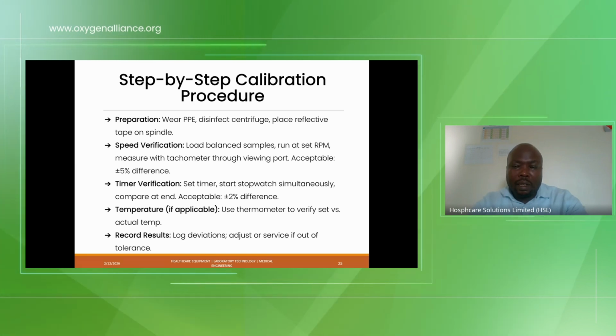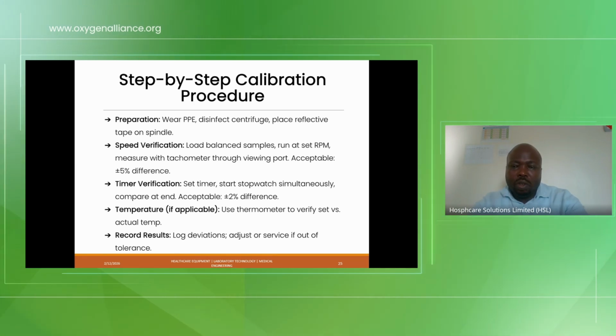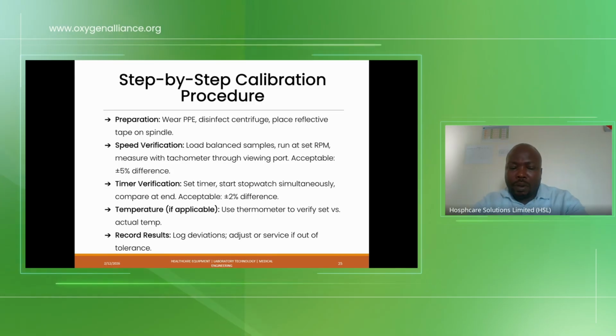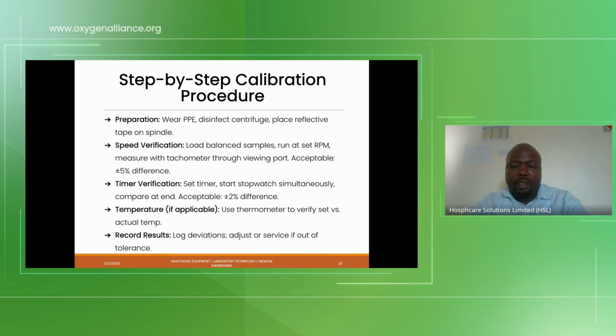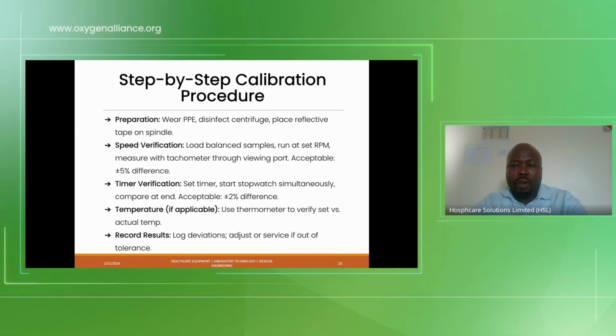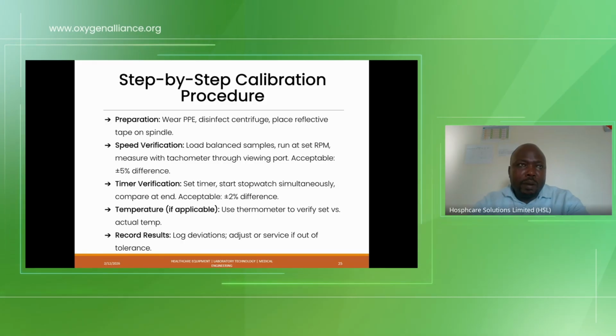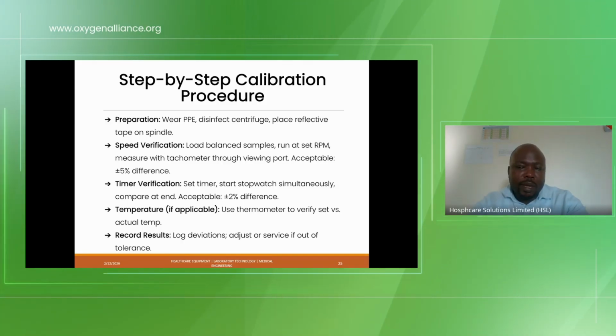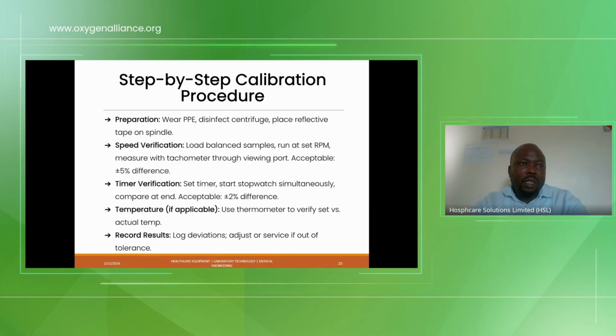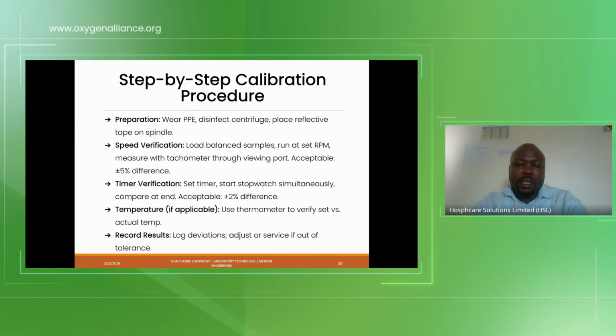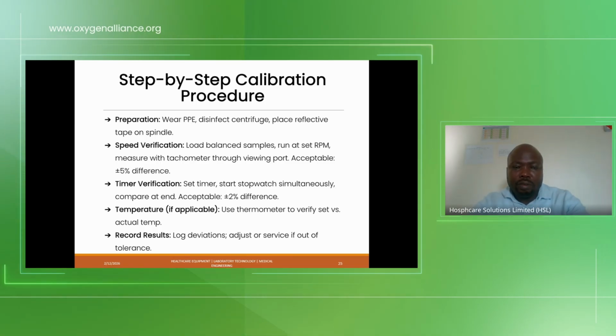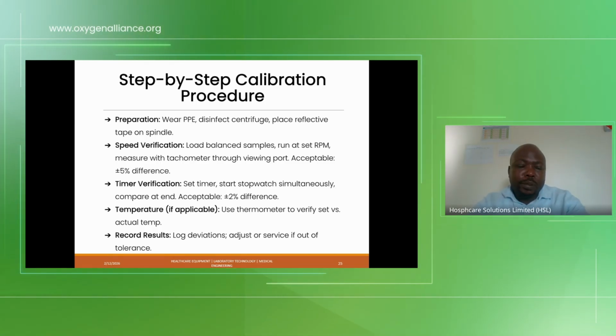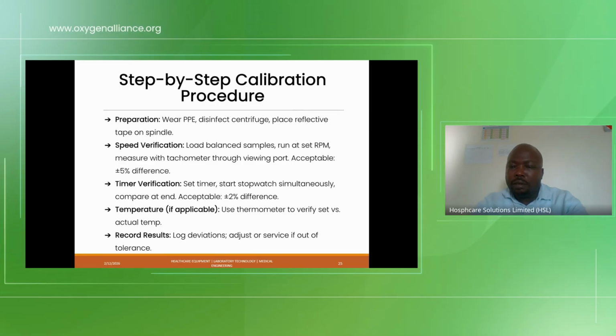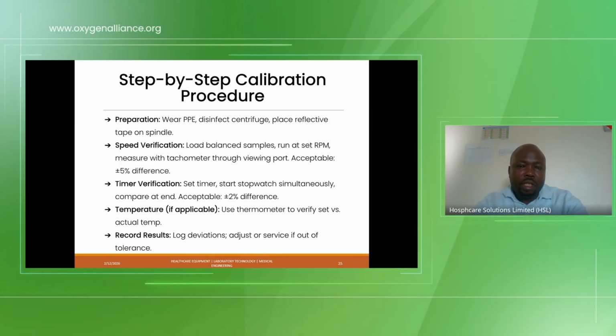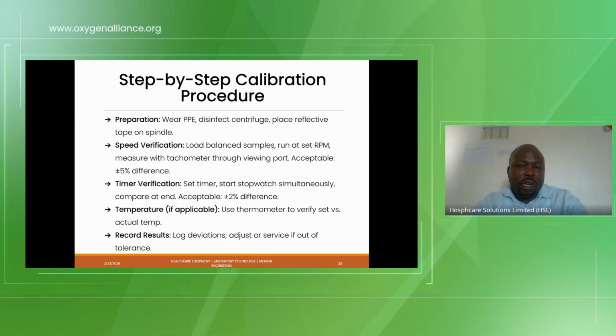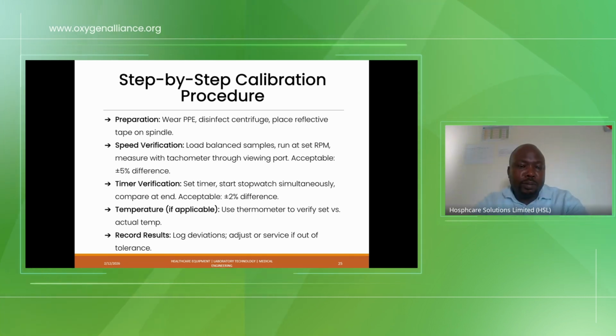You calculate the error in the form of a percentage. Also remember the acceptable error range is plus or minus 5% and below. If the timer error is above this, you need to calibrate by adjusting as advised by the manufacturer. Another important calibration is in temperature, especially for those refrigerated centrifuges. For this one, you'll use a thermometer to verify the set versus the actual temperature.